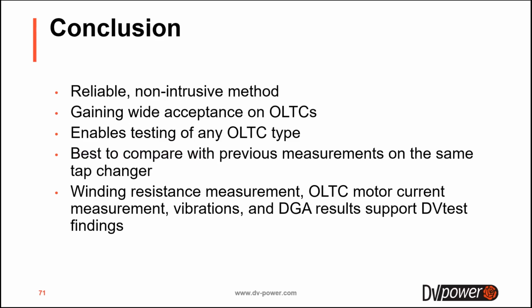So just to conclude, the DVtest proved to be a reliable method because many faults can be detected. It's a non-intrusive method, so you don't have to open the tap changer. You don't have to do a lot of work. You can do it together with the winding resistance without additional time. You can test any type of OLTC. It's a fingerprint method. You can also do OLTC motor current, you can do vibrations, and it's not a replacement method for DGA, so it's a complementary method with all those other testing methods for OLTCs.